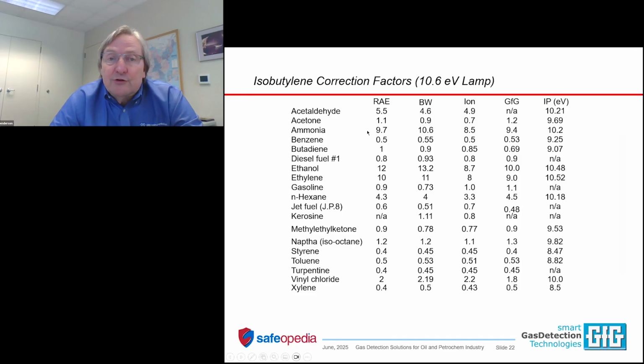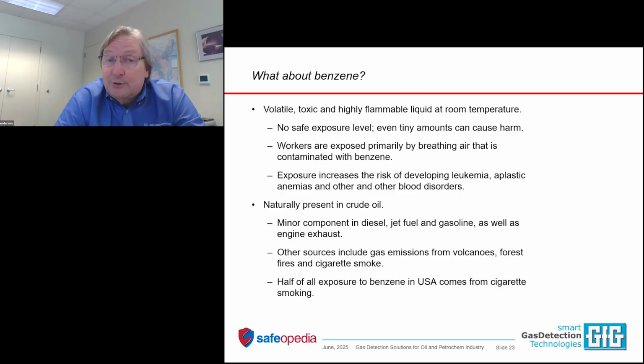If you look at the correction factors for ammonia, for RAE, 9.7, BW 10.6, Ion Science 8.5, GFG 9.4. So you can see there's a pretty good spread. For butadiene, here's another one with a wide spread. Correction factors range all the way from 1 to 0.7 or 0.69. As long as you know what the correction factor required is, all of this comes out in the wash, because the instrument is normalizing the readings to come up to the true concentration. You just don't want to use the wrong table for the wrong instrument. So stick with the materials that came with your product.